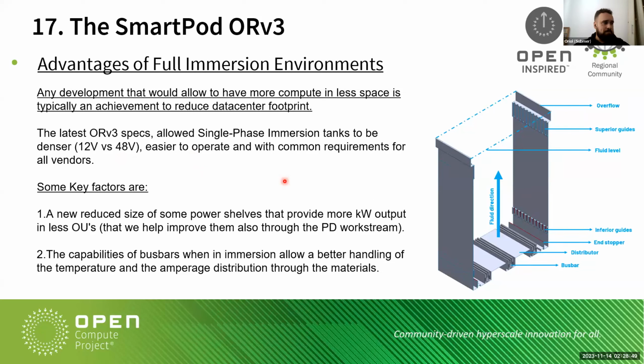The key factors from our point of view: first, we are reducing the size of the power shelf. Before, we needed 3 OU just to give 27 kilowatts; now in 3 OU we can give 54, double that in the same space. Also, the capabilities of the busbars are better in immersion, allowing more temperature and amperage distribution through the same materials.